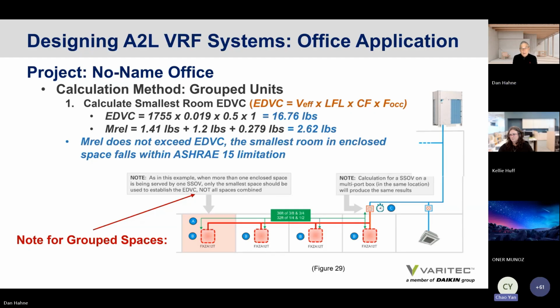Okay, that would be great, because I saw there are 3 numbers here: 1.41, 1.2, and 0.279. Is that it? Just to let you know, it doesn't show which ones those are associated with. One is for the amount of refrigerant in the indoor unit. The other one is for the piping on the gas and liquid. And then the other one is a constant, which is the amount of refrigerant that passes through the valve from the initiation of the event until the end of the event. That's a constant at 0.279 pounds. And those are actually calculated automatically within the selection software. I see.